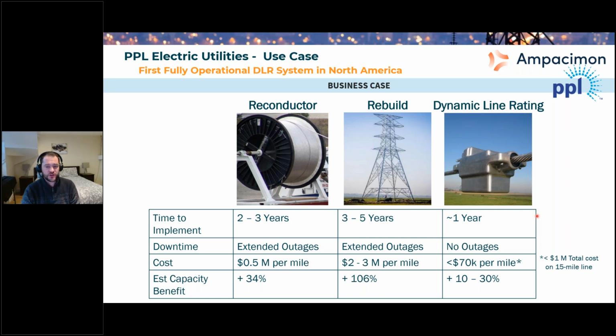This slide is taken from PPL, amended slightly to make it relatable. They had a project looking to reconductor a line, potentially build a new line, or look at dynamic line rating, and they assessed these against each other. Time to implement a reconductoring is 2 to 3 years with lots of outages, at a cost of $0.5 million per mile, giving 34% extra capacity. A rebuild takes 3 to 5 years with extended outages and costs way more per mile, but gives a full doubling of capacity. I'll add that these numbers are quite optimistic.